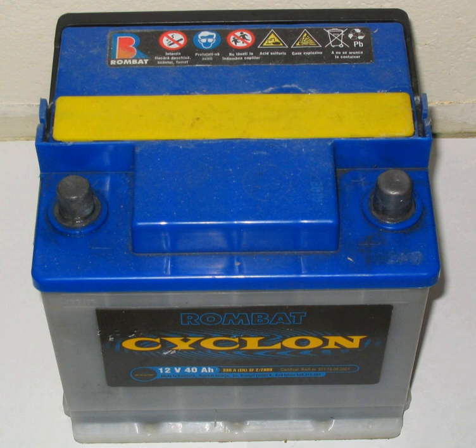Once dry, the plates are stacked with suitable separators and inserted in a cell container. The alternate plates constitute alternating positive and negative electrodes, and within the cell are connected to one another in parallel. The separators inhibit the plates from touching each other, which would otherwise constitute a short circuit. In flooded and gel cells, the separators are insulating rails or studs — formerly of glass or ceramic, and now of plastic. In AGM cells, the separator is the glass mat itself, and the rack of plates with separators are squeezed together before insertion into the cell.